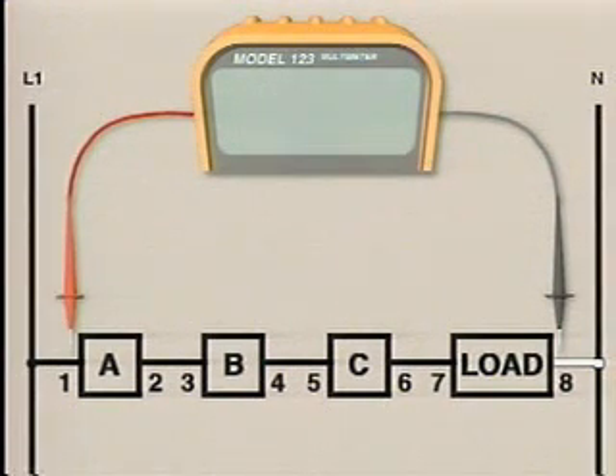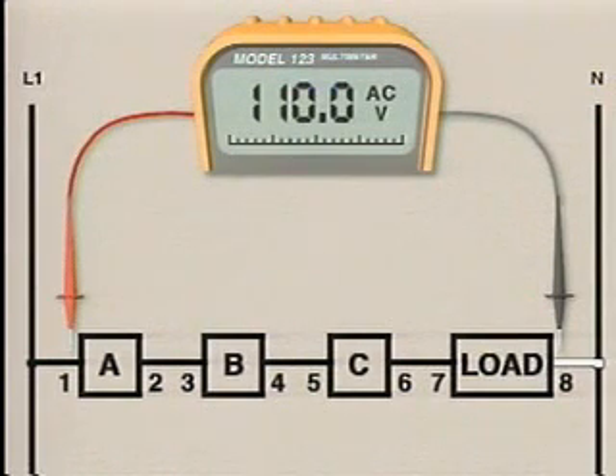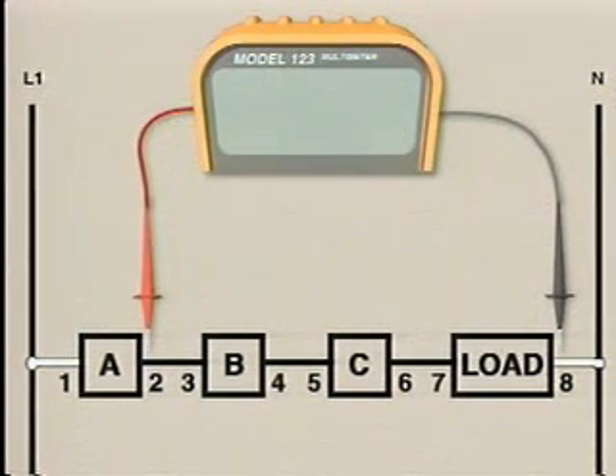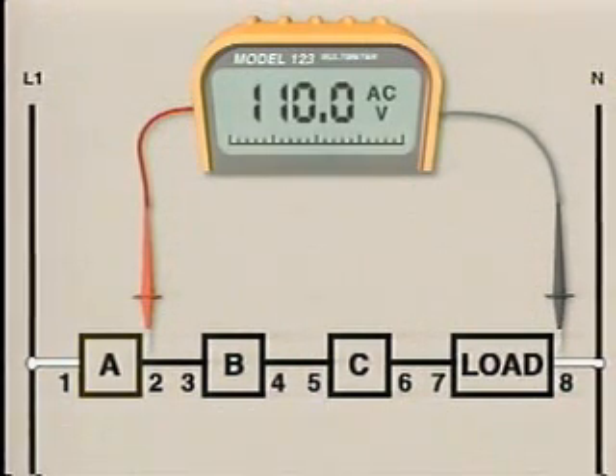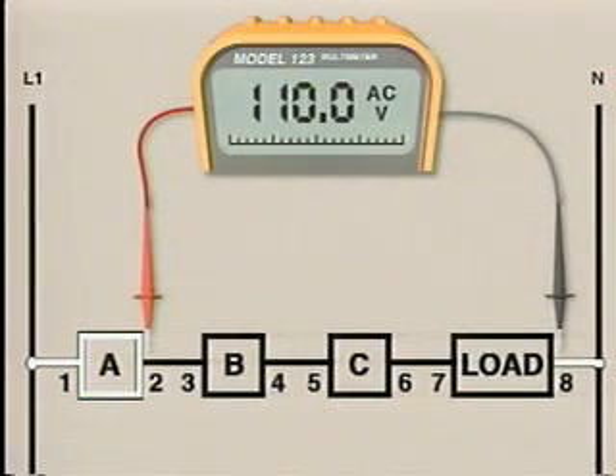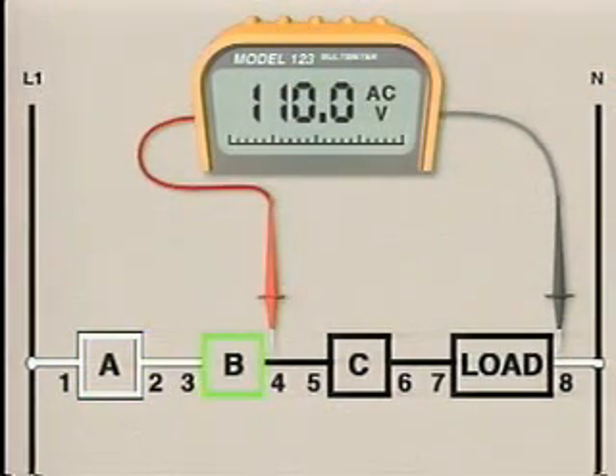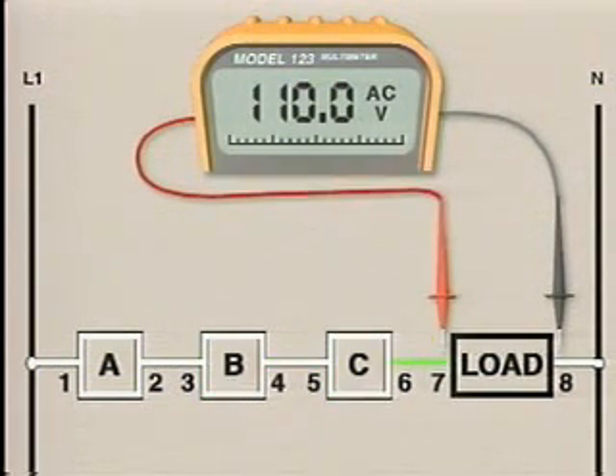We'll start testing the circuit at test point 1. This check will determine if there is a complete path between L1 and test point 1. The voltmeter indicates full line voltage. This means that the wire connecting line lead L1 to control device A is good, so that wire can be eliminated as a possible cause of the problem. The next check would be at test point 2. The result of this test will indicate if the circuit's operating voltage is being applied through control device A. Again, the voltmeter indicates full line voltage. This means that control device A is closed and can be eliminated as a possible cause of the problem. The testing continues, moving along the circuit path one test point at a time until the cause of the problem is found.